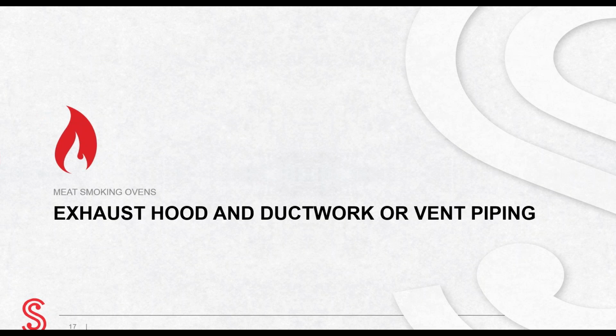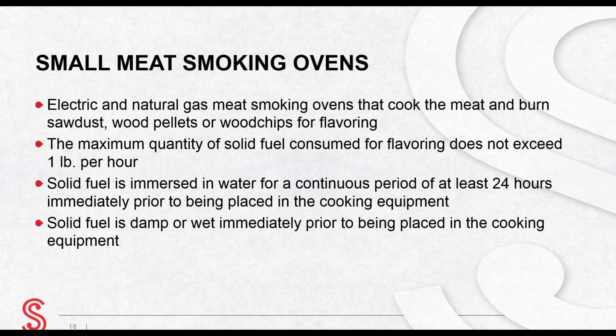We are now going to discuss exhaust hood and ductwork, or vent piping, for small and large meat smoking ovens. What is considered to be a small meat smoking oven? They are electric and natural gas meat smoking ovens that cook the meat and burn sawdust, wood pellets, or wood chips for flavoring. In small meat smoking ovens, the maximum quantity of solid fuel consumed for flavoring does not exceed 1 pound per hour in a gas or electric smoke generator rated at 100,000 BTU per hour of burner capacity.